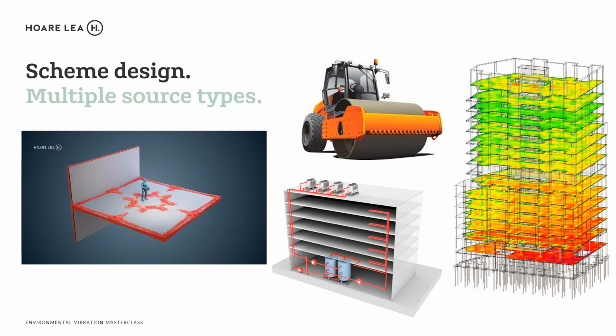We've dealt with projects in the past where we've had to really get hold of a construction program and essentially curtail that construction program to make sure that certain limits didn't affect mass spectrometers, in this instance, in a scheme that was affected by this. Then there is an understanding of how the vibration can propagate through a structure. So that's kind of the plot on the right.